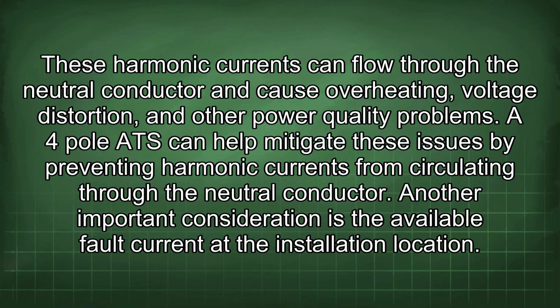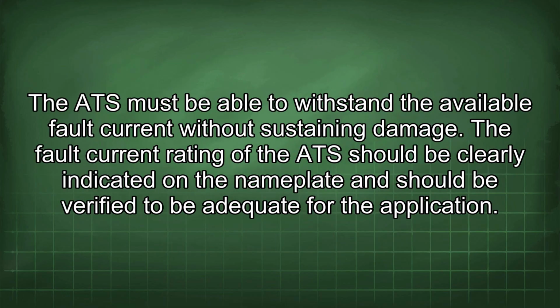A 4-pole ATS can help mitigate these issues by preventing harmonic currents from circulating through the neutral conductor. Another important consideration is the available fault current at the installation location. The ATS must be able to withstand the available fault current without sustaining damage.